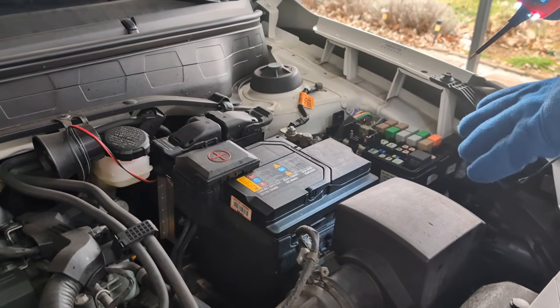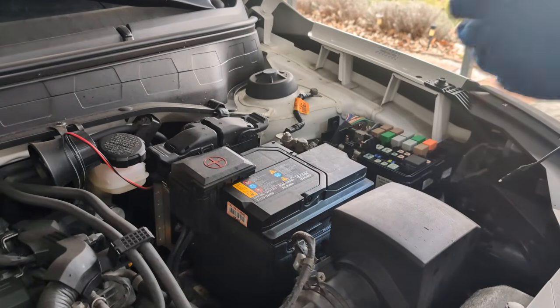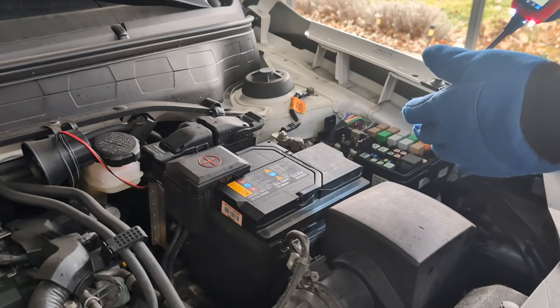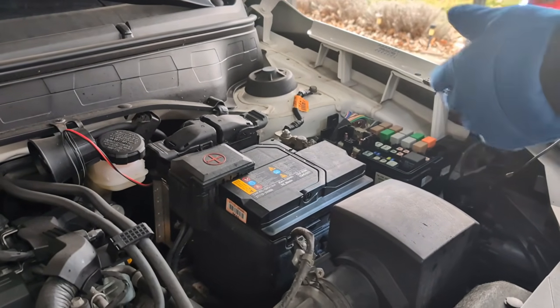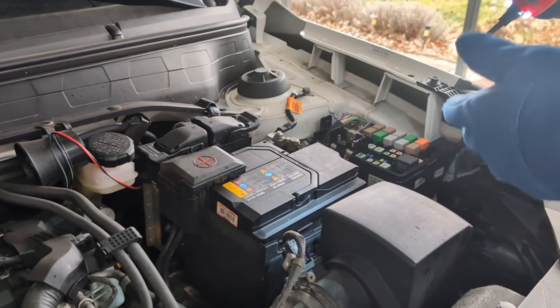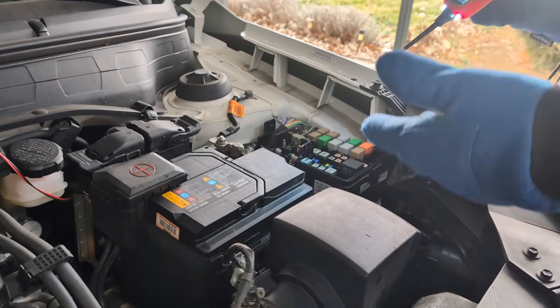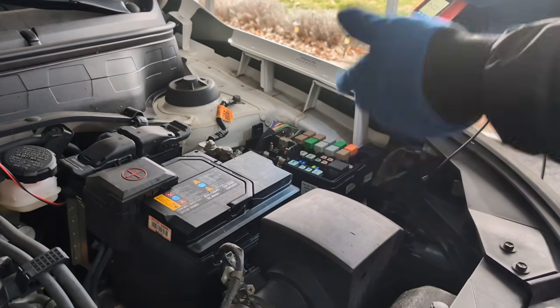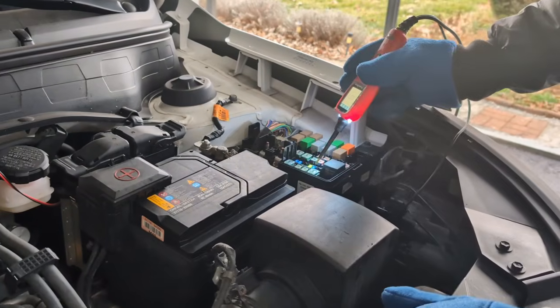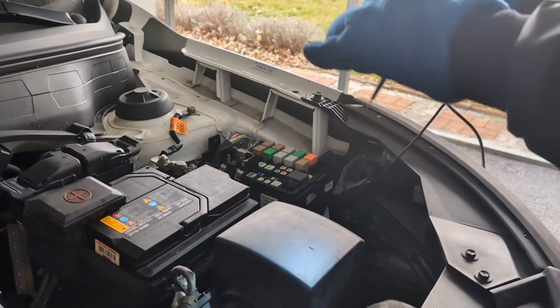If you're not getting voltage and you should be, you need to trace back and see what the problem is. If you are getting voltage and you shouldn't be, you need to find out why. You can also use this to check if you think a fuse is blown, are you getting voltage? If I'm getting voltage here, but I'm not getting it there, then you probably got a blown fuse.